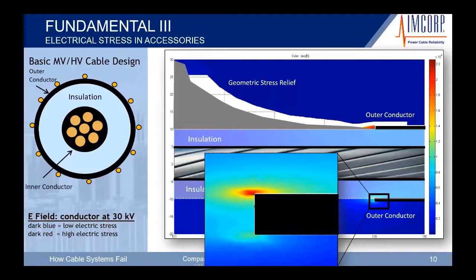So today we use a geometric stress control, which is these push-on type of components, but still used today in some of the newer splices that are out there and some of the load break or dead front elbows that are installed. It's a lot of conductive material that goes over the semicon with a lot of insulation, and it has this geometric stress control, or geometric shape, that redistributes that electrical field, so it reduces or eliminates any electrical stress in the termination. Also, impedance, it's a very low profile.